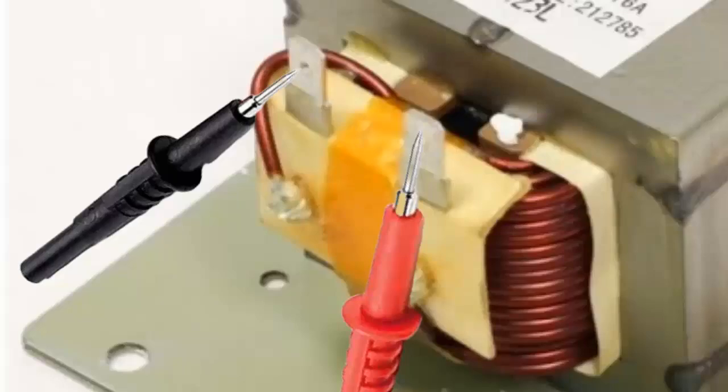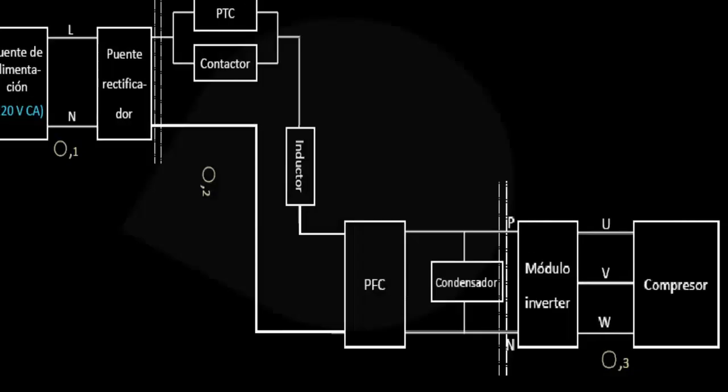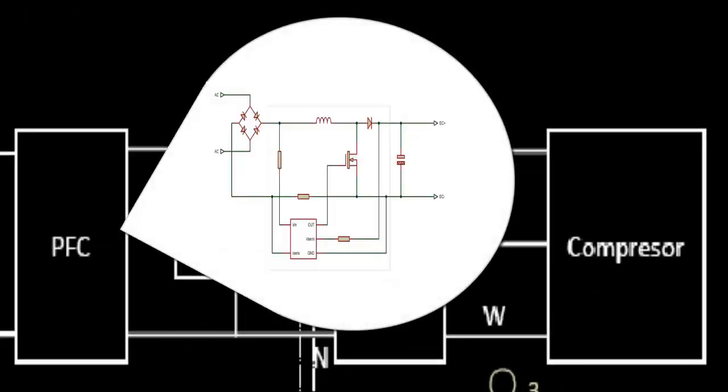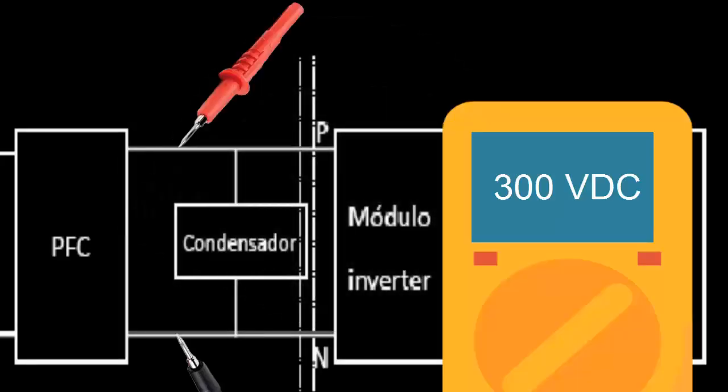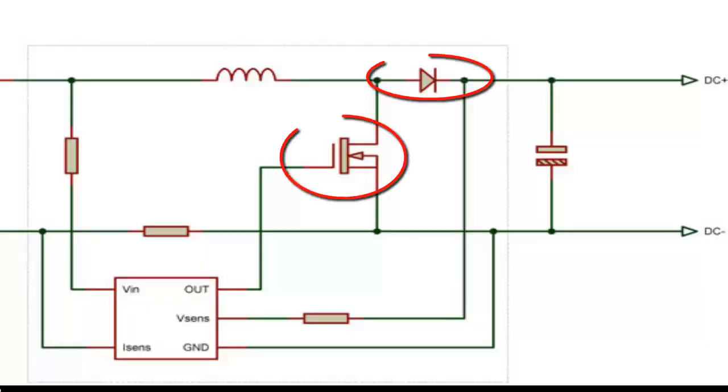Point 7: The PFC circuit is crucial for improving energy efficiency, reducing interference, and stabilizing the equipment's operation. Test the output voltage of the PFC circuit, check the state of the recovery diode, and observe the condition of the IGBT transistor.